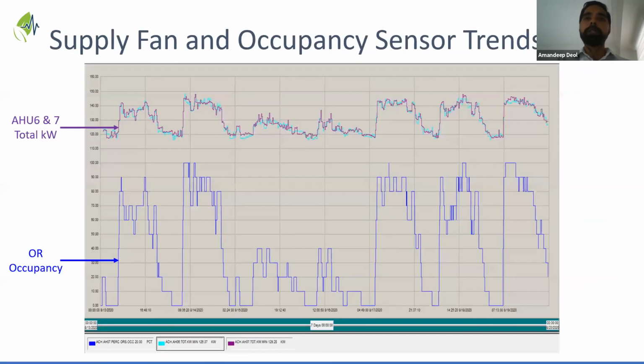So what you see on this graph is the 2 units that are feeding the operating rooms, and on top is the supply fan and total kilowatts for the supply and the return fan. As you can see, it goes from the range of 140 kilowatts to 120 kilowatts at nighttime when unoccupied. It matches the occupancy schedule in that space.